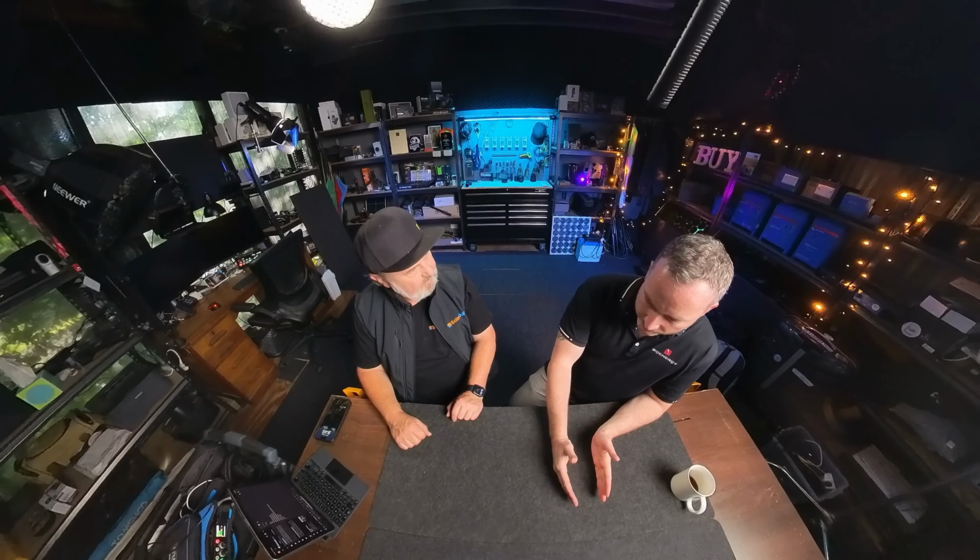We haven't talked about the PV side though. So it's hybrid. How many inputs do they have? So it varies. On the 5 and the 6, we have 2 MPPTs. On the 8 and the 10, we have 3 for single phase. And on the 3-phase, we go from 2 on the smaller ones up to 4 on the 15 and 25. Wow, 4 MPPTs on the bigger unit. So that gives you the flexibility of long strings. Yep. And I think this year, don't get too excited, but I'm pretty sure it's going to happen, we'll be going to 1,000 volts on domestic. Woohoo! Looking forward to that. Nice long strings will make the job of installers a lot easier.